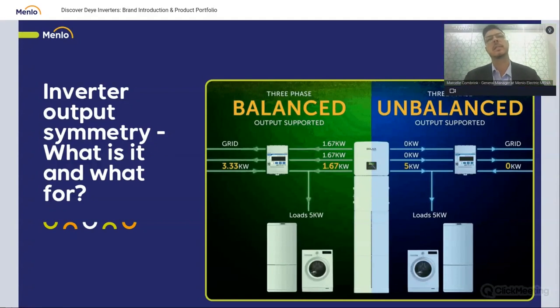Inverter output symmetry. What is this about? A lot of systems that you install from all the manufacturers are balanced systems. So what does it mean? If you have a load of 5 kilowatt and three phases, and those three phases deliver 1.6, 1.6, and 1.6 kilowatt, only one phase will go physically to the load. The other two phases will export to the grid, and then the system needs to import the balance of the 3.3 kilowatt to fulfill your load needs.